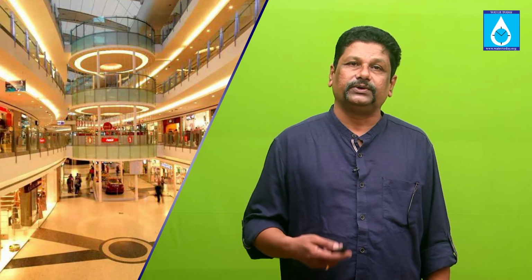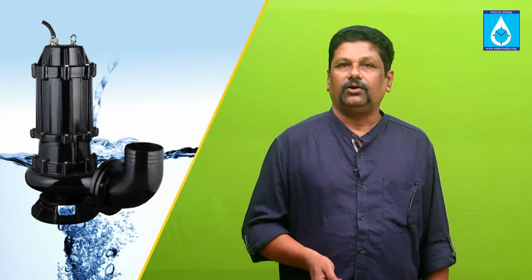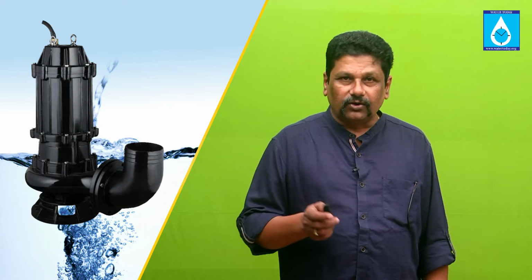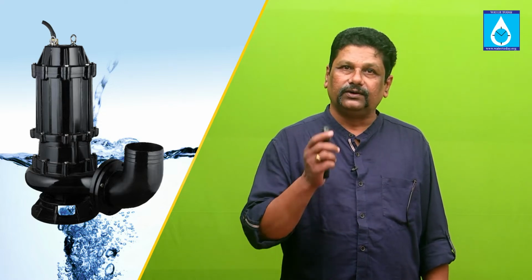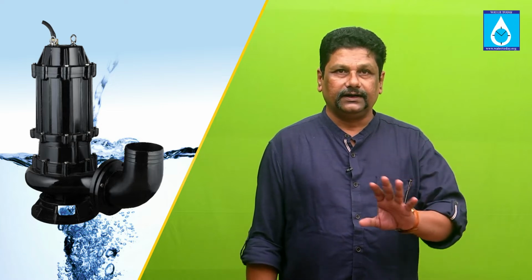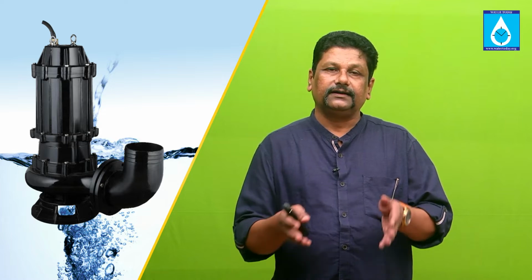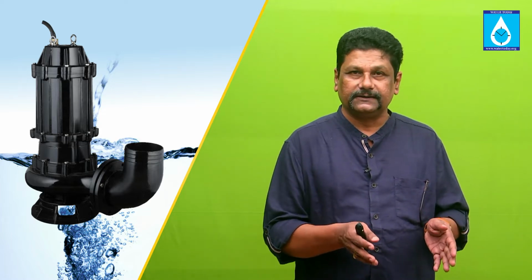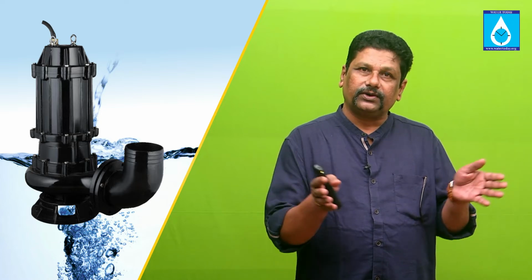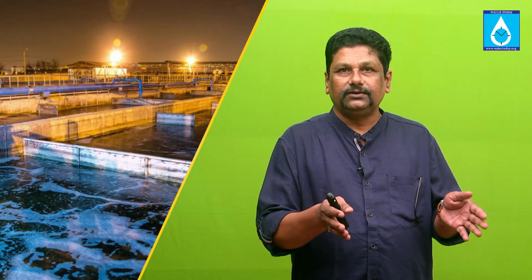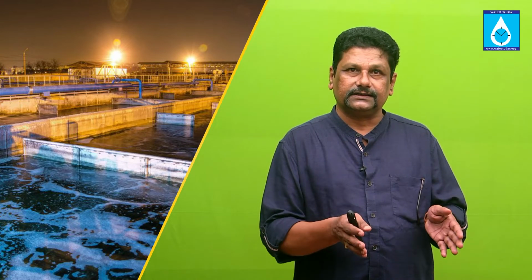Positioning the pumps in the sewage pumping pit is one of the most important things if you want your sewage pumps to last longer and longer. If you follow all this, even your sewage pump will work for 15 years without any problem, provided you do the normal maintenance prescribed by the manufacturer. The first and foremost is the center to center distance between the 2 pumps. The Hydraulics Institute gives you this. You can't put them further away, or too close together. You need to maintain this center to center distance.